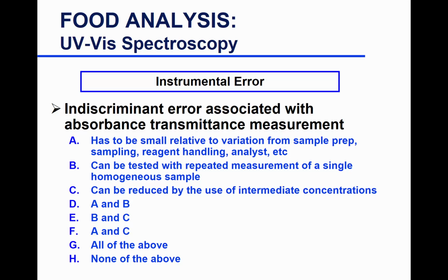You really want to go back and dilute your samples or standards to make sure that absorption is between 0.2 and 0.8. That's kind of the ideal absorption, between 0.2 and 0.8. Some instruments are sophisticated. You can get an absorption of 1.5, for example, but you still can get low noise, depending on how old your spectrophotometer is and the make of the spectrophotometer.